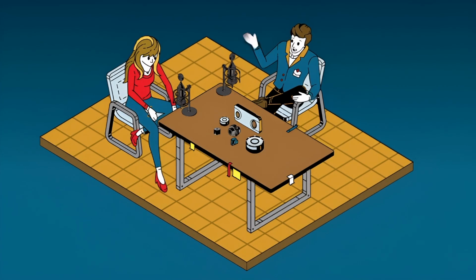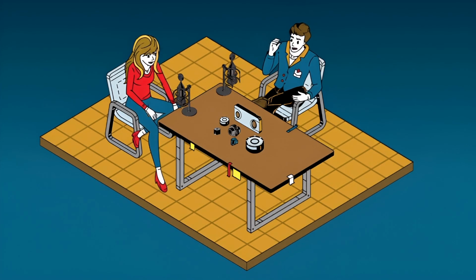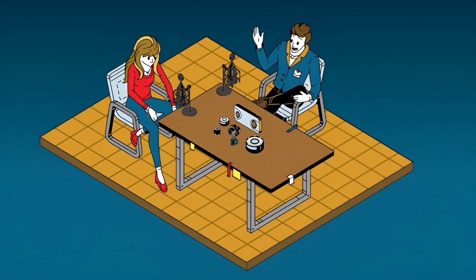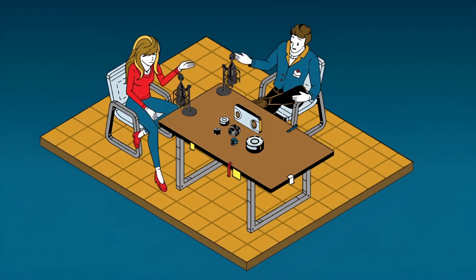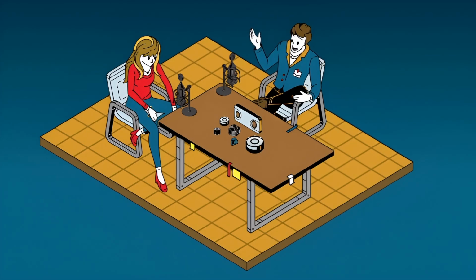The miniature load cell serves as that missing nervous system, providing tactile feedback. If a robotic pincer is grasping a delicate blood vessel, it needs to know the exact micro pressure being applied in real time so it doesn't just crush the tissue - which would be catastrophic. So the miniature load cell embedded in the pincer measures that tissue resistance, that tiny fraction of a pound force, and feeds it back to the operating system instantly.